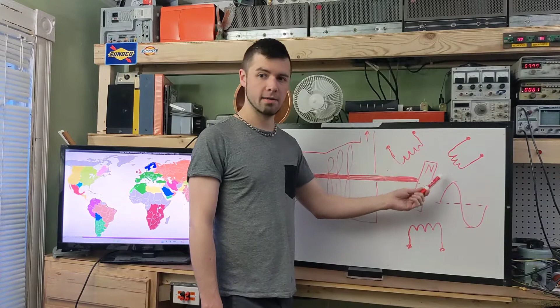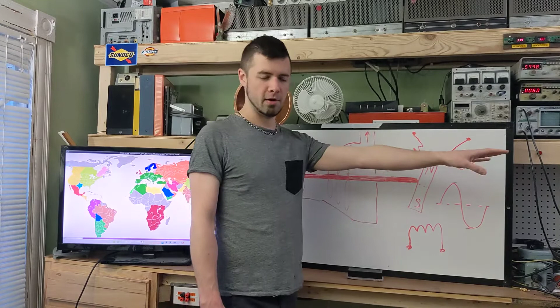So the way that the natural gas plant gets started is they take these coils of the generator in the power station, and they energize them from the transmission lines that are being fed from that hydroelectric power plant. The hydroelectric plant is producing a sine wave pattern like we just looked at on the scope over there, and that basically lights up these coils with electricity, and it causes this magnet to start rotating.